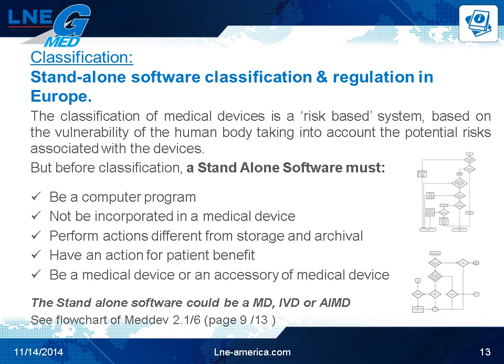The classification of medical devices is a risk-based system based on the vulnerability of the human body, taking account of the potential risks associated with the devices. Before classifying a device, standalone software needs to be evaluated to determine first if it's a medical device. To be considered a medical device, the software must be a computer program, not be incorporated into a medical device, perform actions different from storage and archiving, have an action for the patient's benefit, and be compliant with the definition of a medical device or accessory as outlined in the directive. Standalone software could be a medical device, an IVD, or an active implantable medical device. For further guidance, refer to MEDDEV 2.1-6, which contains flowcharts for this determination.